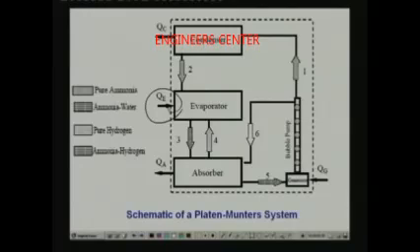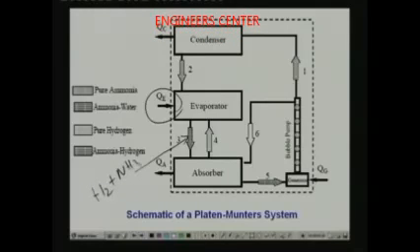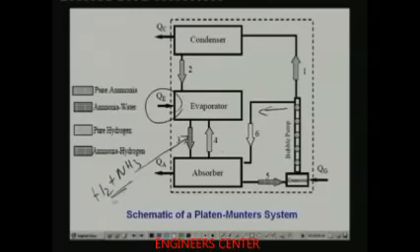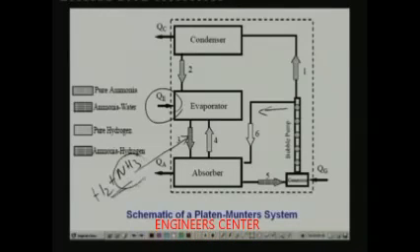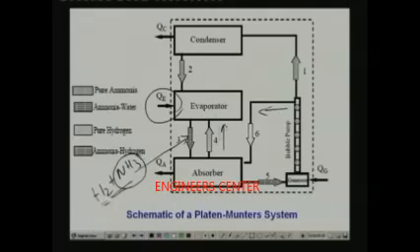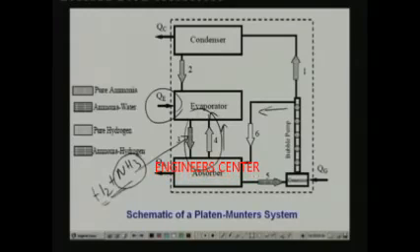As ammonia evaporates, a vapor is formed. The cooler mixture of hydrogen and ammonia vapor goes down due to buoyancy and flows to the absorber. In the absorber, the weak solution coming from the bubble pump contacts the hydrogen-ammonia mixture. The solution absorbs ammonia but cannot absorb hydrogen, so hydrogen is left out. As hydrogen absorbs heat, its temperature increases, it becomes lighter, and rises back up to the evaporator - maintaining closed hydrogen circulation by buoyancy.